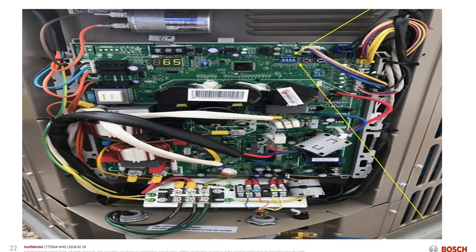This is my board. A lot of people at this point go, whoa, that's a board. I tell people all the time, this is not your grandpa's unit. What you're seeing there at the 65, that particular number, if my unit was off, that number would be recording the outdoor ambient temperature. If the unit was on, that number would represent the frequency, or the hertz rating, of my compressor. Where the yellow arrows are, those are 4 dip switches. I have the chance to, what we would call, dial in my unit if I needed to.